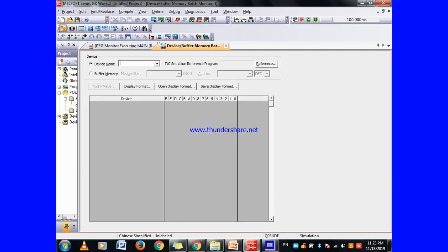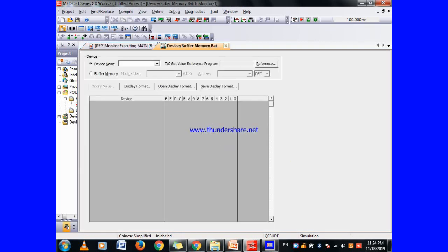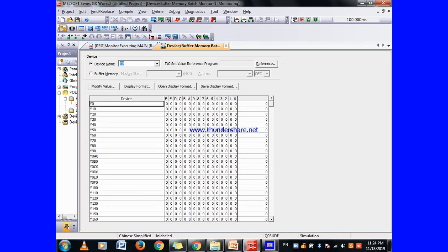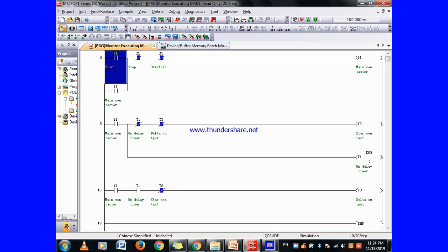If you want to check any output, you can also see it from the online device buffer. I'll write the addresses here so you can watch them. Starting again — you can see Y1 getting on, Y2 getting on, and after 8 seconds Y3 also gets on. You can see Y1 and Y3 on together when in delta mode, and when we press stop everything goes off.